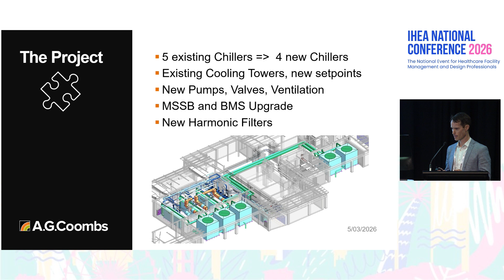Off the bat, some of the challenges we had to work within: during the project, we had to maintain the chill water supply to the hospital. At least 3 of the chillers needed to be available at all times, and of those chillers we needed to provide at least the duty capacity on generator supply.